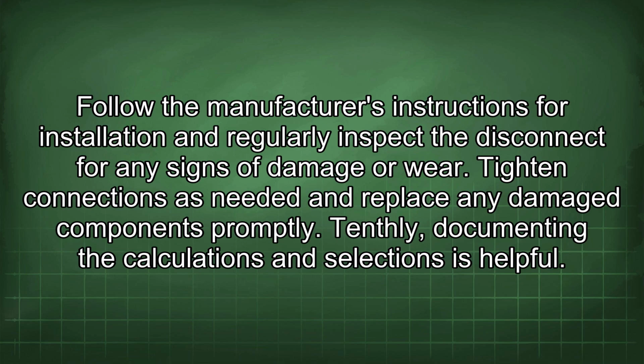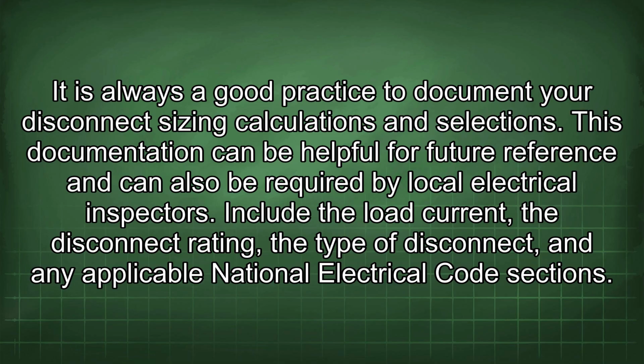Tenthly, documenting the calculations and selections is helpful. It is always a good practice to document your disconnect sizing calculations and selections. This documentation can be helpful for future reference and can also be required by local electrical inspectors. Include the load current, the disconnect rating, the type of disconnect, and any applicable National Electrical Code sections.